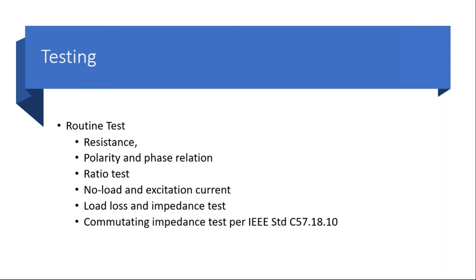Same way, the no load losses and load losses. The no load losses are exactly the same. You supply one of the windings with the rated voltage. However, the load losses are different, because now you have multiple sets of load losses. One is for total, with all secondary windings shorted and supplying the rated current based on total MVA of the transformer. That is the total losses and the total short circuit impedance of the transformer. Now, in order for us to get to commutating impedances, we have to measure the impedance of each winding with respect to the primary. So if a 3-winding transformer has 2 LV windings, then there are 2 sets of ratings. When we have 4 or 6 LV windings, then you have that many ratings from each secondary to the primary.